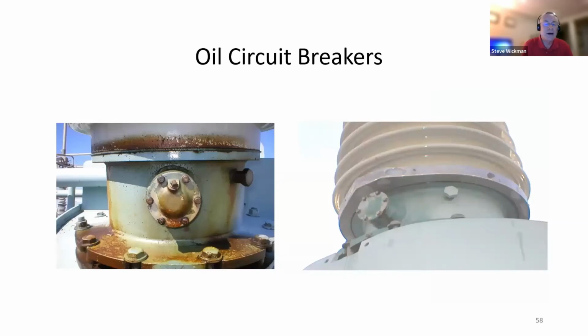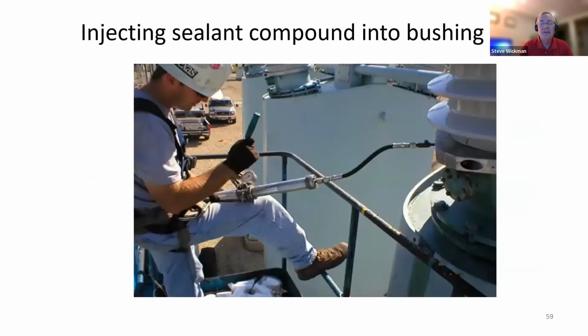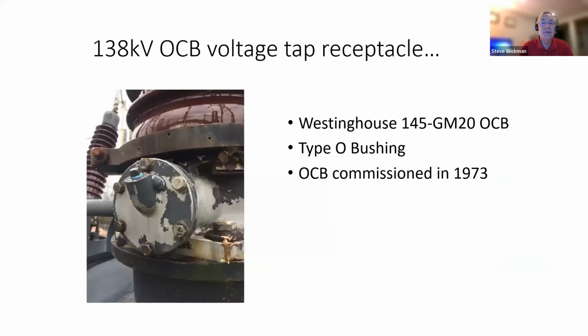The most popular leak, you might say, is this flange and interface between the porcelain and steel. You can see the leaking bushing on the left, and you can see the clamp in place in the one on the right to address that situation. Here's sealant compound getting pumped into that bushing clamp on this breaker here. Notice the next pole over has got another clamp in place. Again, effectively doing the repair there.